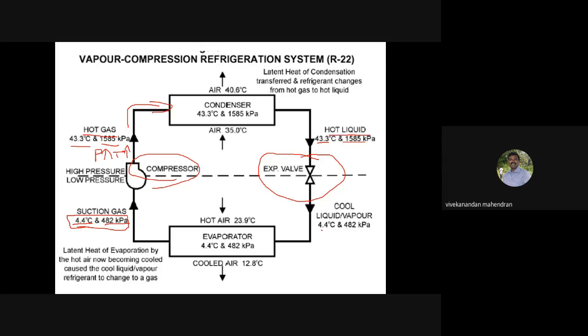So that is why it comes to 4.4 degrees. How does it go from 43 to 4.4 degrees without any heat input? By general thermodynamic principles of pressure, velocity and temperature, it changes to 4.4 degrees and reduces to 482. So now this is liquid. You can't compress a liquid, so since we're holding a compressor here, it has to be converted back into gas.